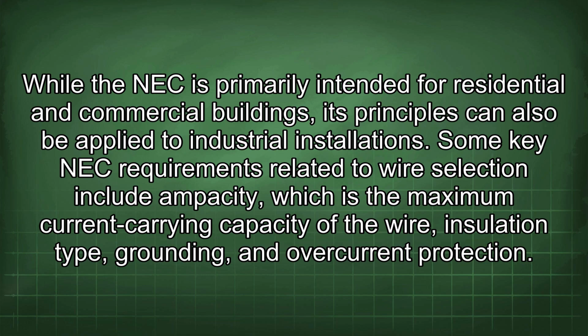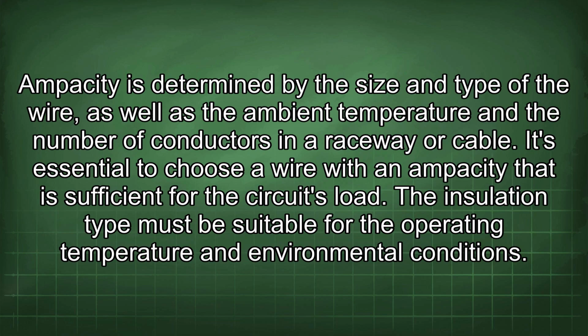Some key NEC requirements related to wire selection include ampacity, which is the maximum current carrying capacity of the wire, insulation type, grounding, and overcurrent protection. Ampacity is determined by the size and type of the wire, as well as the ambient temperature and the number of conductors in a raceway or cable. It's essential to choose a wire with an ampacity that is sufficient for the circuit's load.